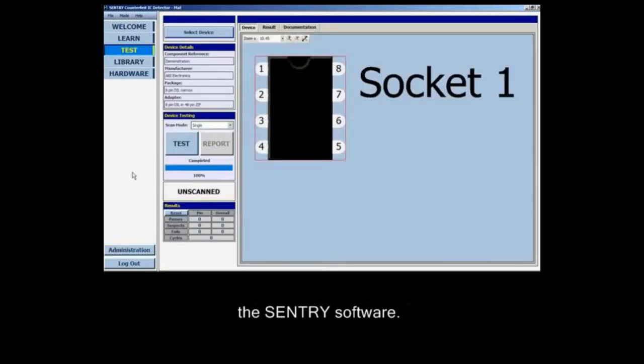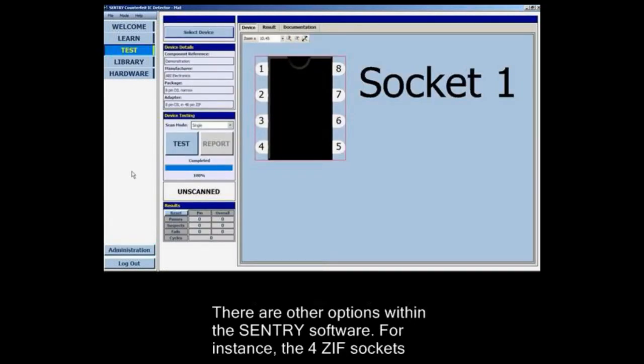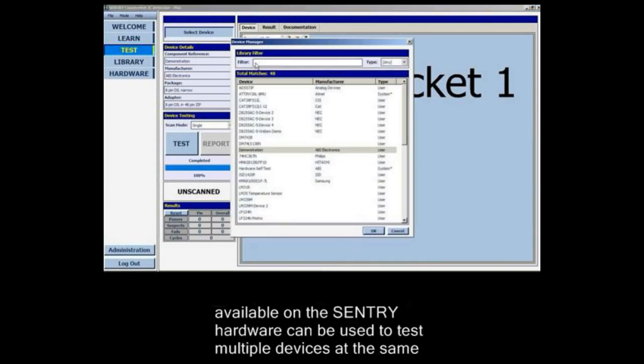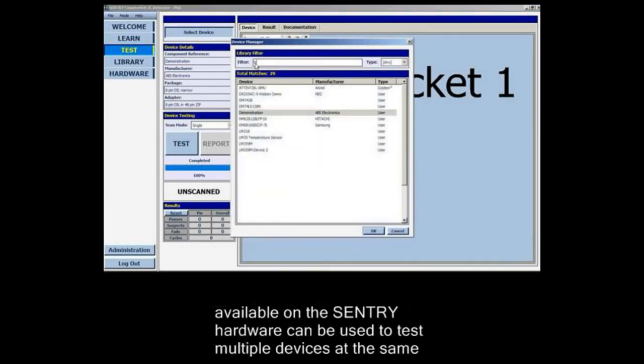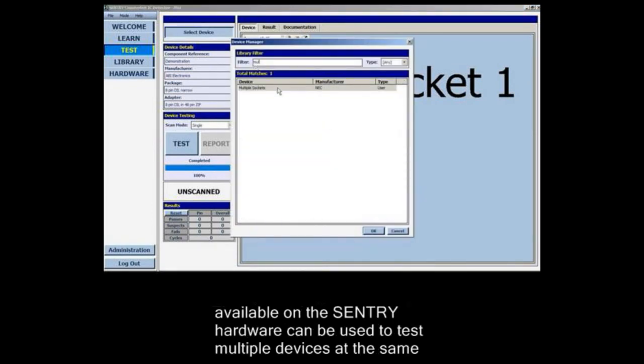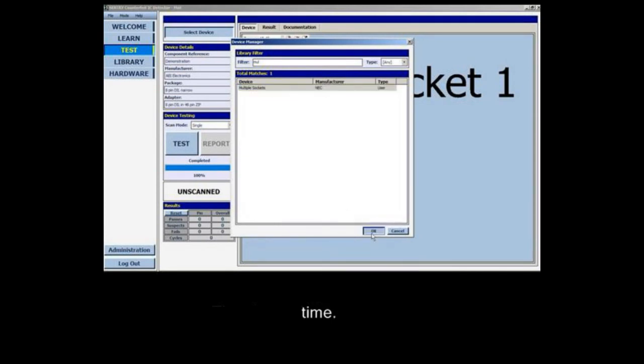There are other options within the Sentry software. For instance, the four ZIF sockets available on the Sentry hardware can be used to test multiple devices at the same time.